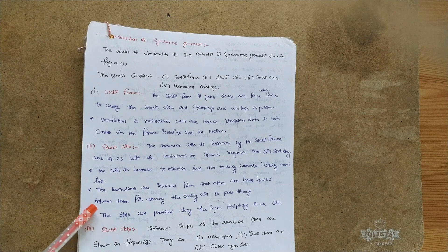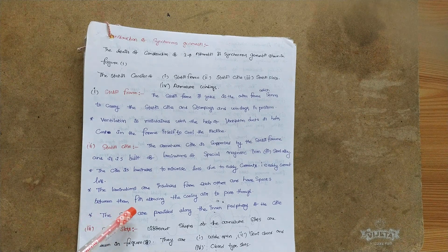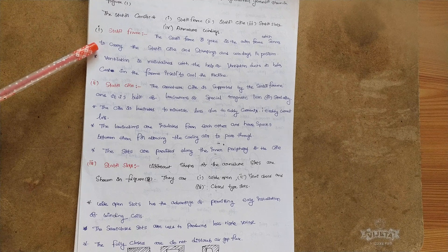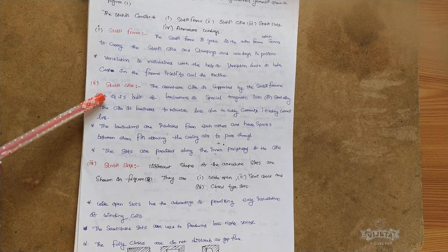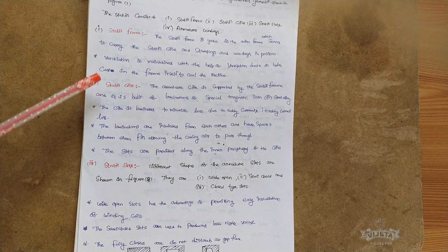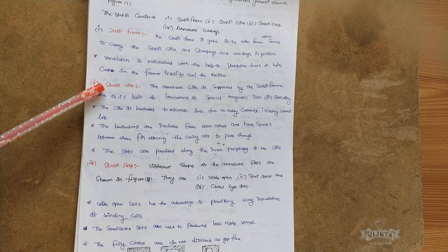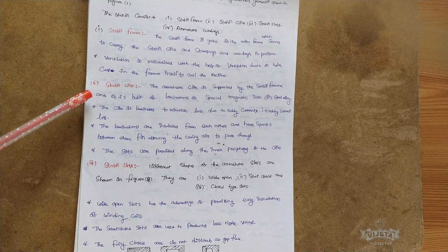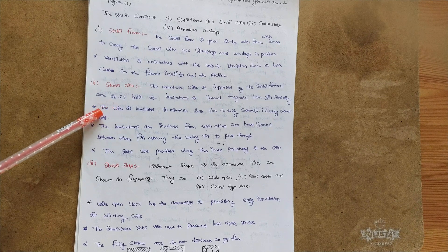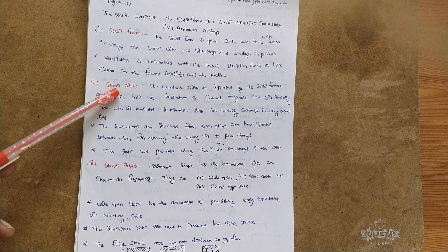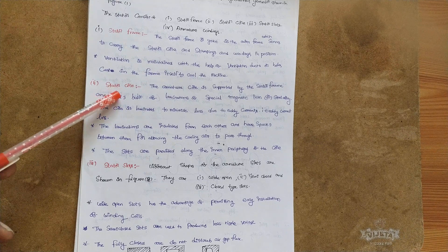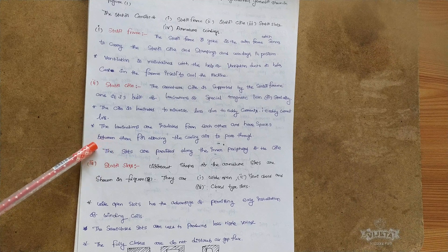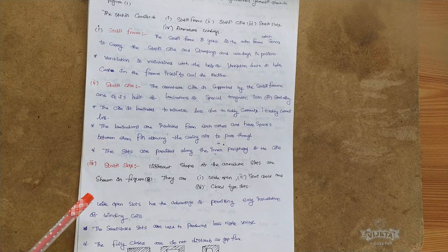The laminations are insulated from each other and have spaces between them for allowing cooling air to pass through. Slots are provided on the inner periphery of the stator core. The stator frame houses the stator core, stampings, and ventilation ducts. The stator core is made of steel alloy or magnetic iron - a magnetic material is required since the stator also carries magnetic flux. Laminations reduce eddy current losses and allow cooling air flow.